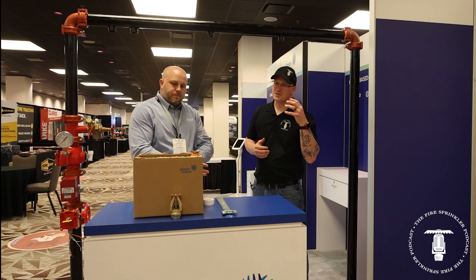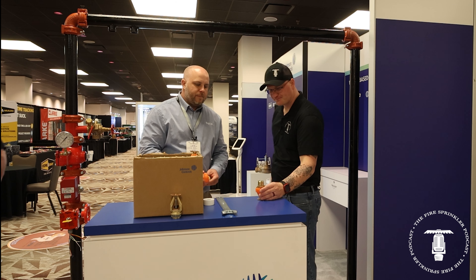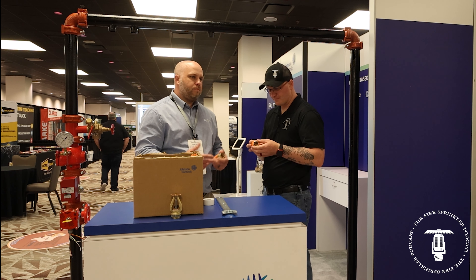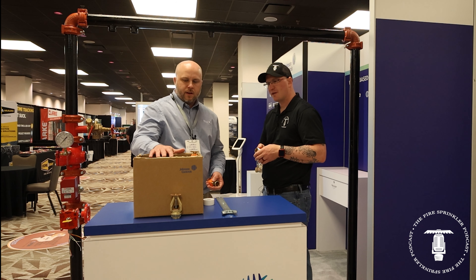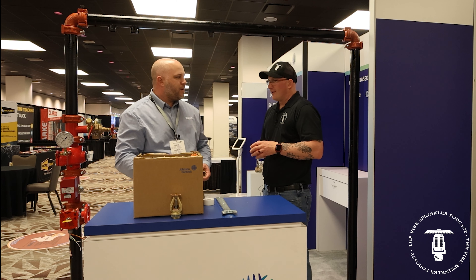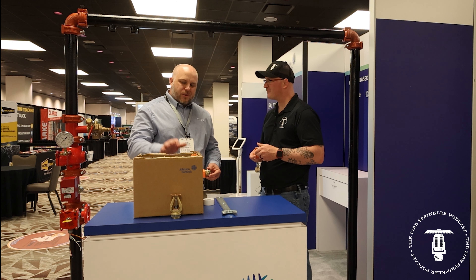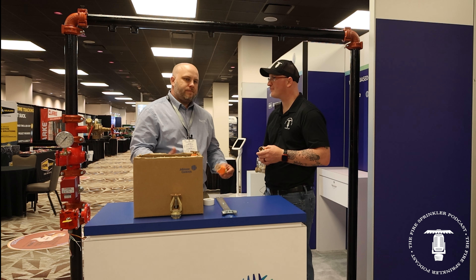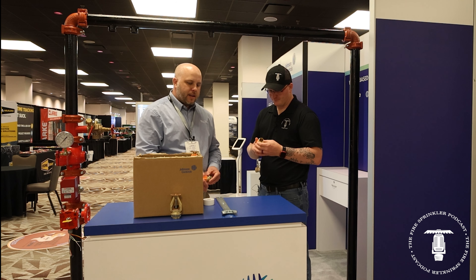So what are the benefits of using the Rapid Seal versus a standard ESFR sprinkler if we're looking at them side by side? Number one, there's no Teflon tape or dope required — you take a whole step of prep out of it. If you were to tape and dope this box — and most fitters on one-inch outlets tend to do both — you're going to be about 16 minutes a box. And with 50 heads to a box, you can do the math.